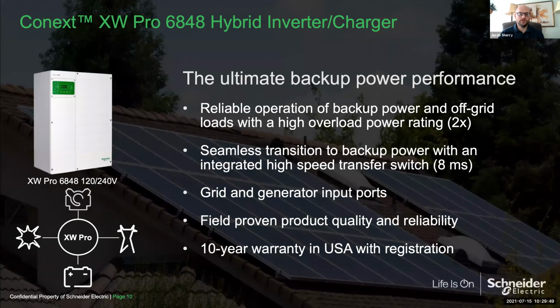So the key with the XW Pro is that you're really getting unparalleled backup power performance. In grid connected applications, and especially with off-grid loads, you may have surges that require over 2 times the continuous power rating of the inverter, and the XW Pro is able to meet that surge requirement due to a large toroidal transformer, which provides that surge capability. Also internal to the XW Pro is a high-speed transfer switch, which is rated at 8 milliseconds response time when transferring over. If the grid is lost and you're switching to backup power, it would take only 8 milliseconds, which is usually a flicker-free response time.